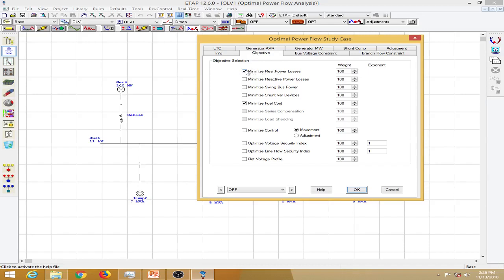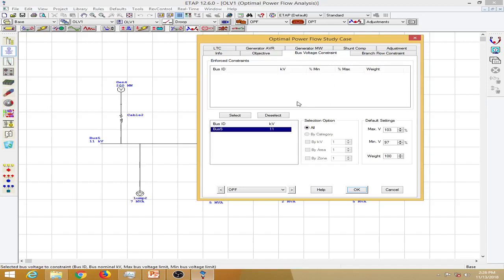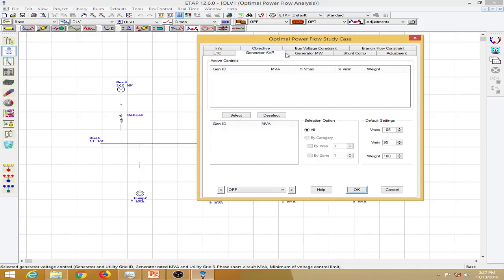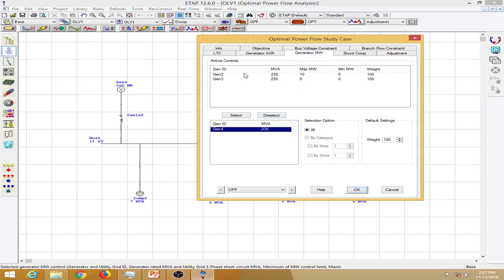I have selected the objective constraints: minimum real power losses with 100% weightage, minimum reactive power losses, and minimum fuel cost. I have selected these three constraints, each with 100% weightage. For bus voltage constraints I am not providing any constraint for now. We can also provide branch flow constraints to limit power on the cables, and generator MW constraints — here minimizing the cost for generator 2 and generator 3.